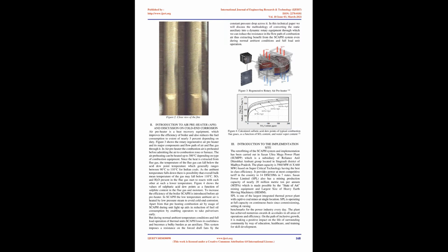This type of equipment is normally incorporated into the design of a boiler unit for low-load operation, and it can be used during unit startup operation also. It has fin tubes which increase the heat exchange surface area. It is generally located in the duct between the forced draft fan and the air preheater. Figure 1 and Figure 2 show the arrangement of the fins in the tubes of SCAPH.